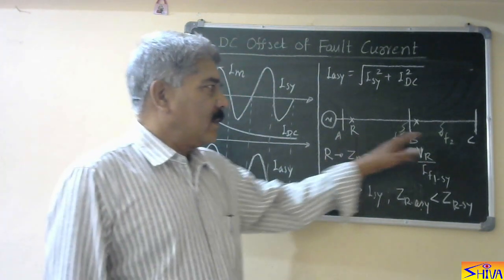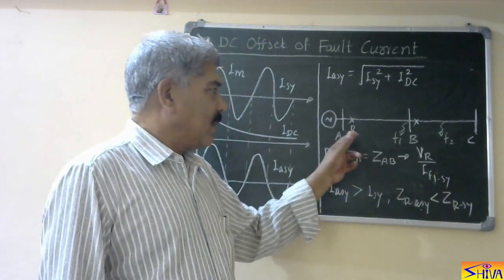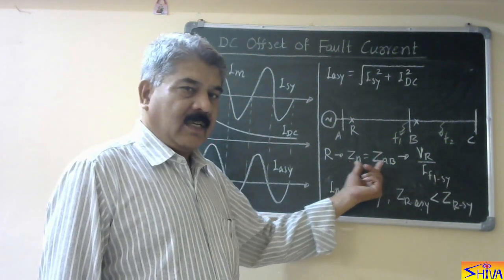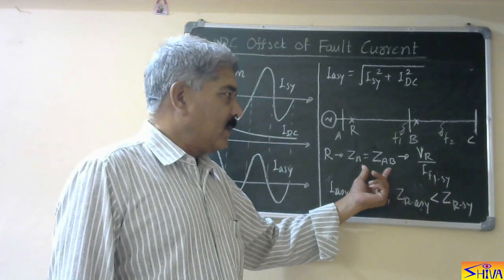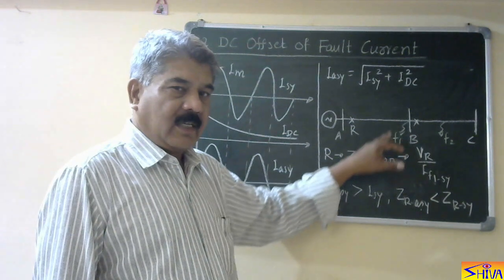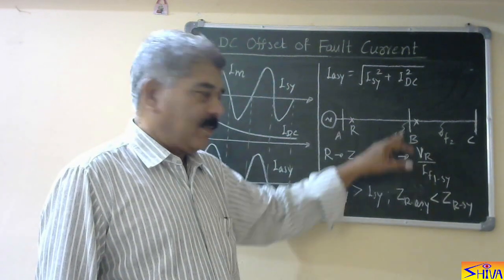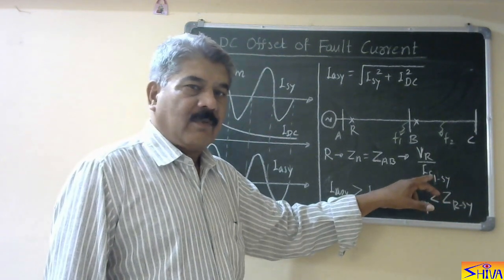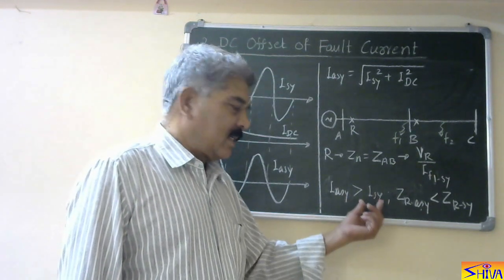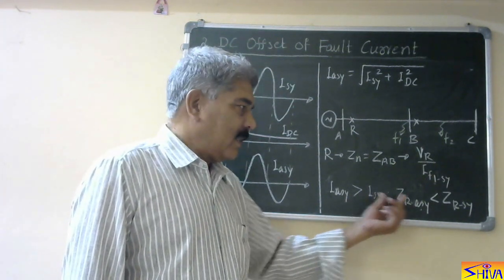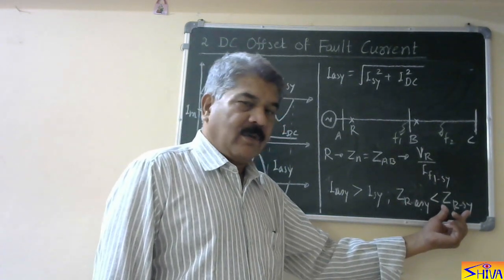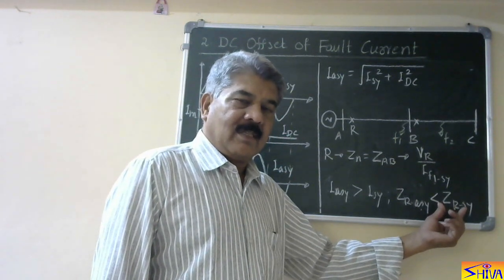Now let us consider this power system with two sections: AB and BC. Relay R is used to protect line section AB, so its reach — the impedance setting — is equal to Z_AB, which is Vr upon I_F1. It is set according to the fault current magnitude at the extreme end, and that fault current magnitude is the symmetrical fault current magnitude. Now when an asymmetrical fault current is present, it is greater than the symmetrical fault current. Therefore, the impedance measured by the relay due to asymmetrical fault current is less than that measured with symmetrical fault current.